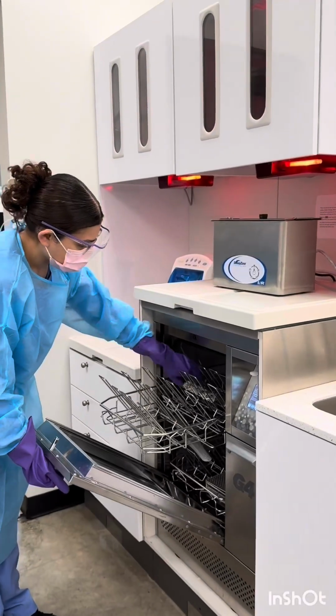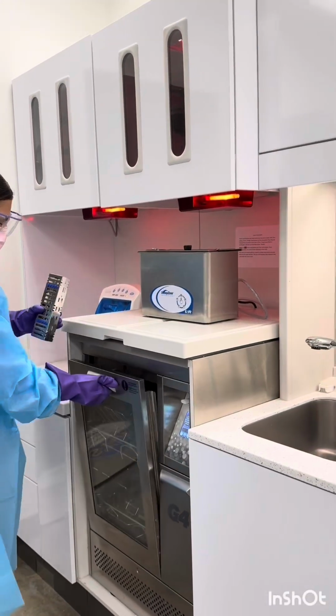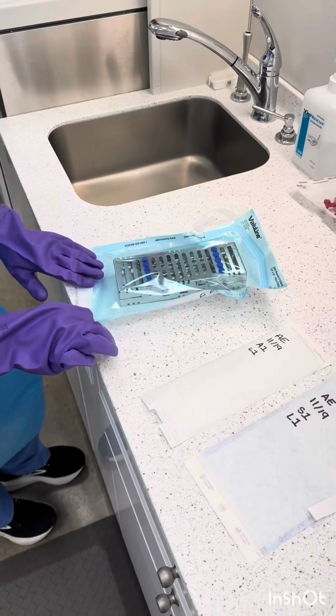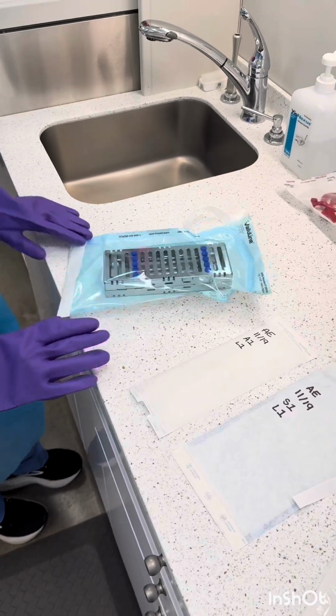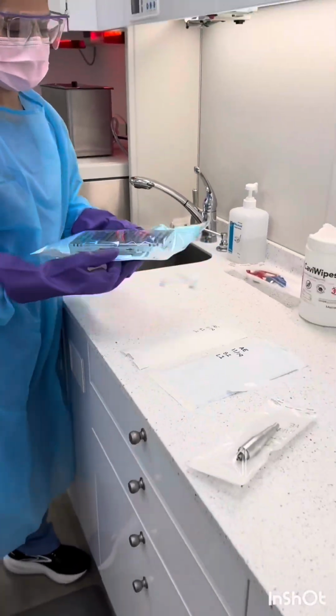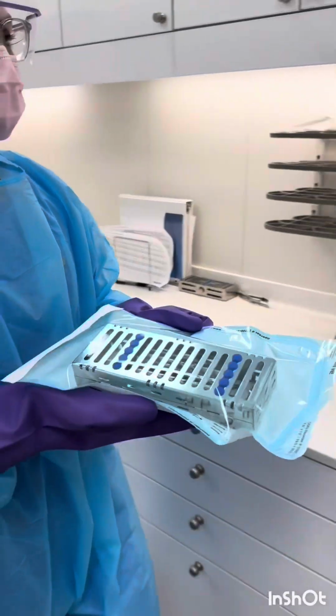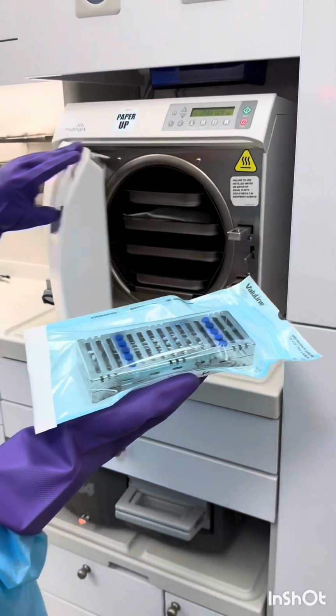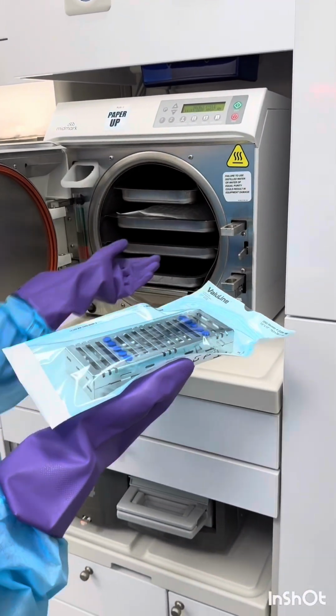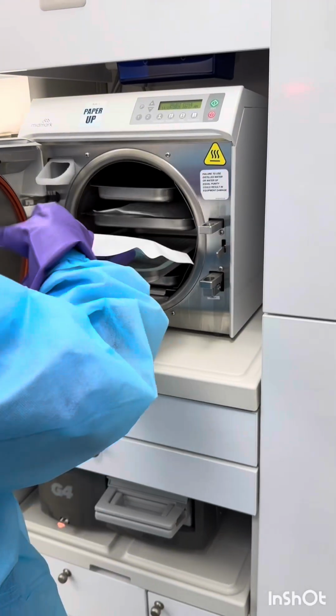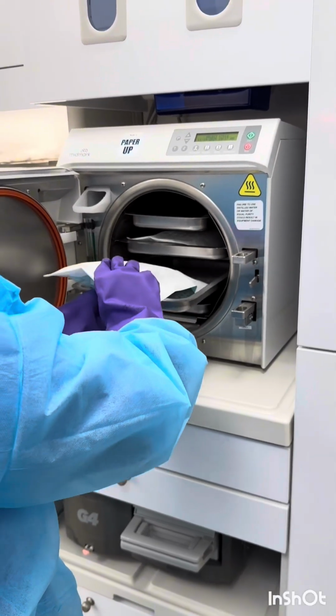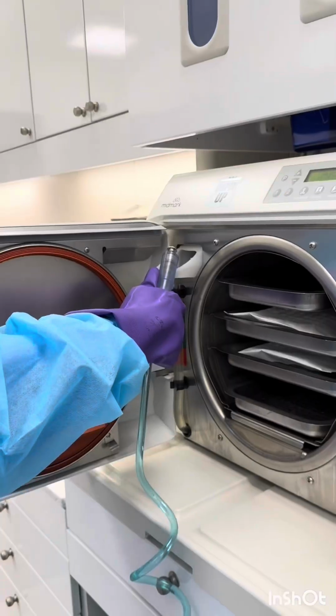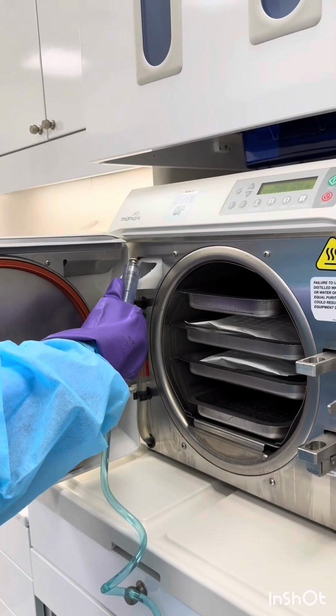At this point, the Hydrim should be done. We can remove our cassette and place it in its proper packaging, again making sure there is enough space for the heat to properly flow through. We will now begin filling the autoclave, making sure packages are paper side up. Again, you always want to make sure to check your water levels and refill them if needed. The autoclave will run for 45 minutes and reach a temperature of 275.